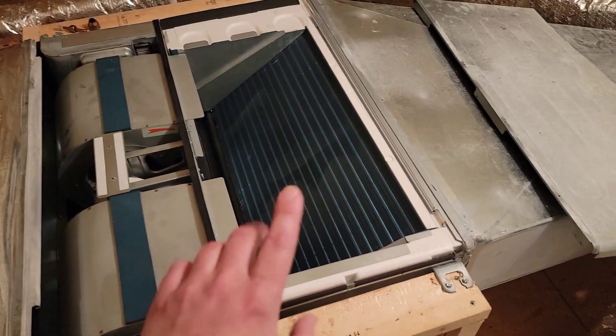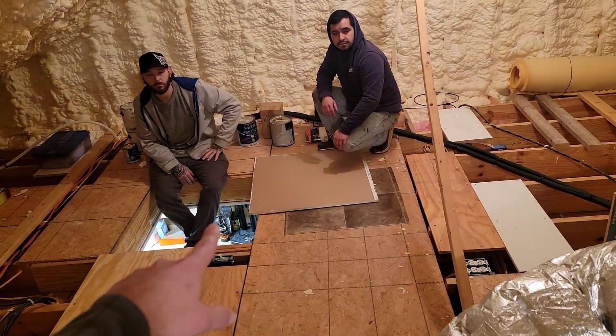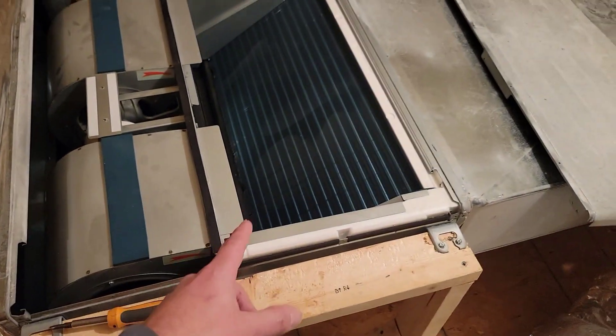It's open because we just finished pressure testing. Got Nick and James here — they found the leak. Was it hard to find? Nope, took about 10 minutes. I was here last week and I could not find the leak, so I cut out the flare connections outside and re-flared, thinking maybe that's the problem. I actually put 600 pounds of pressure, and I guess that leak got bigger and bigger between last week and this week.